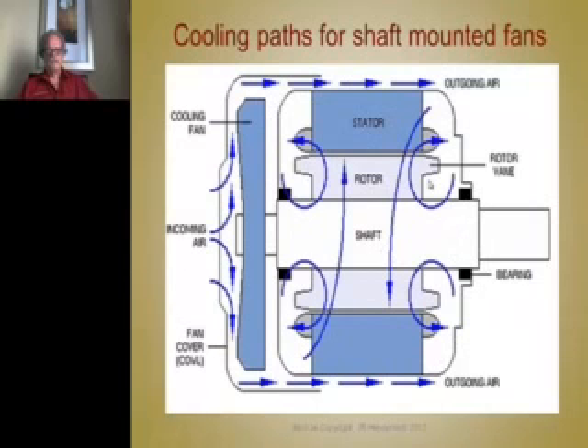But this die-cast rotor has, they call it vanes on this item, but it's basically fan blades that have been die-cast on a rotor. We've seen that before. And when this rotor spins, it's a centrifugal fan that blows air around here and cools the end turns, and that air heats up pretty fast, but due to its motion, it flows on the inside of the stator, or the end bell there, and of course convection on the outside takes the heat away as that heat is conducted through the thickness.